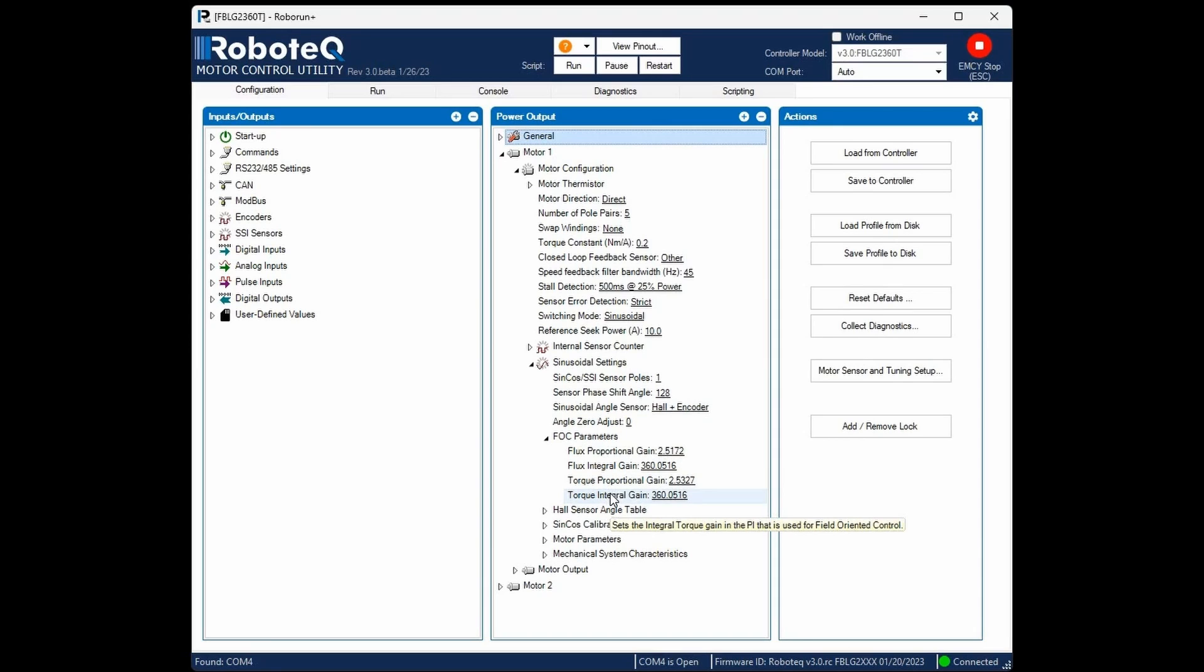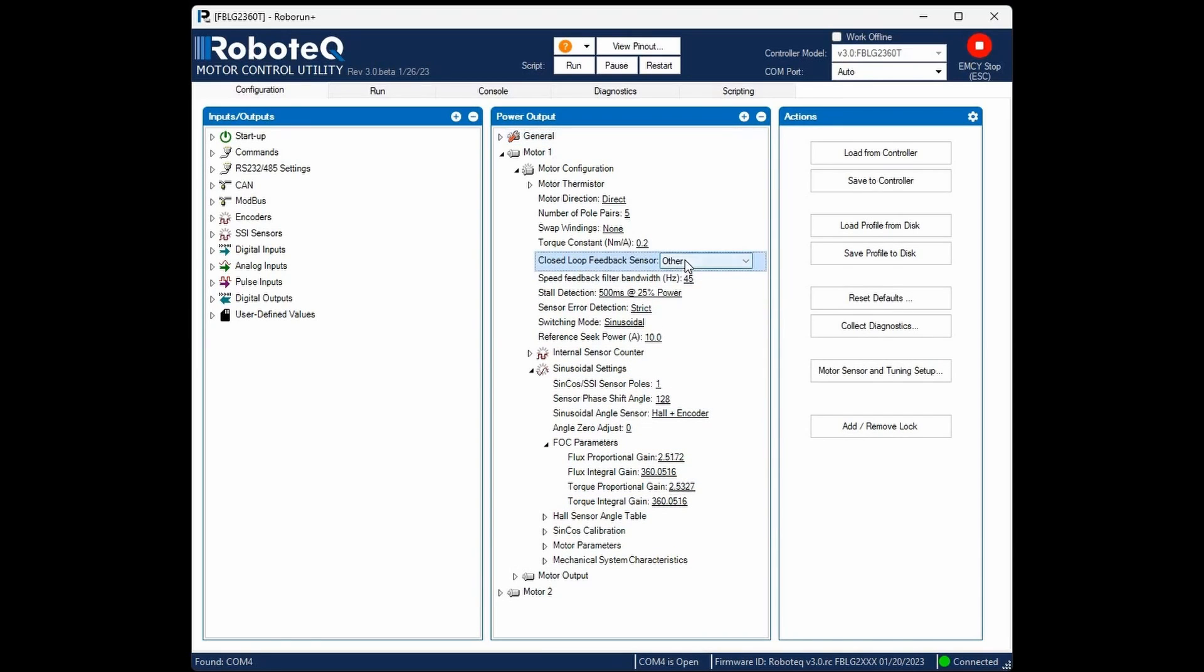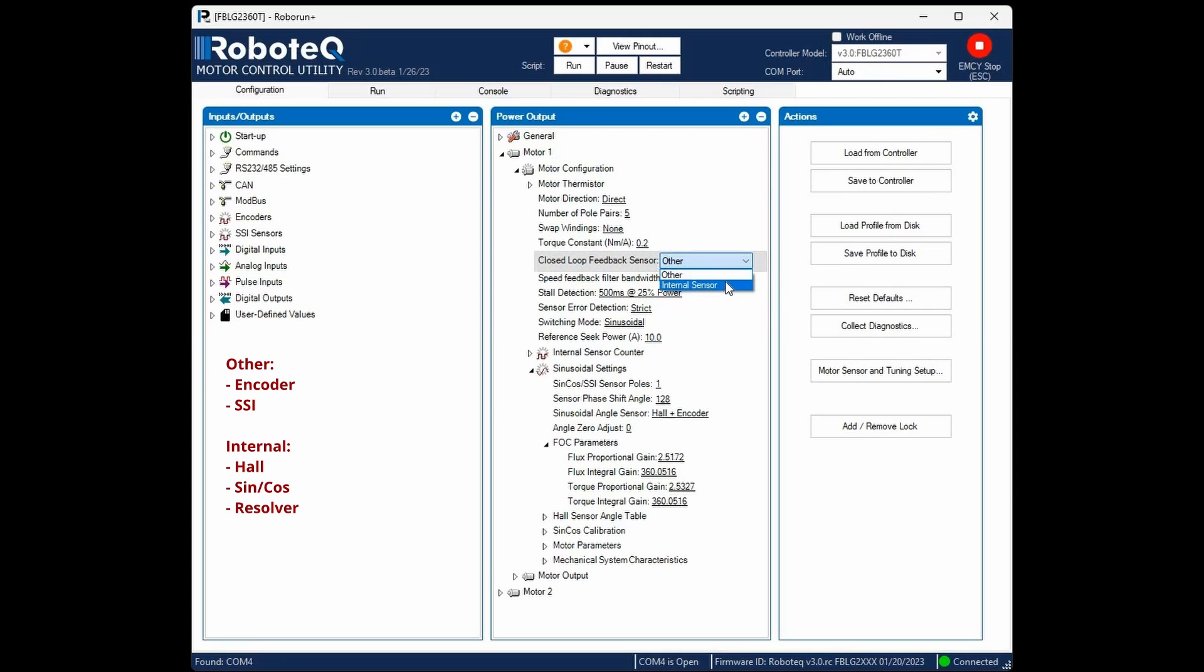Navigate to the closed loop sensor setting and configure the sensor that will be used for the closed loop operation. The other option corresponds to quadrature encoders and SSI sensors, while internal relates to hall, SinCos, or resolver sensors.